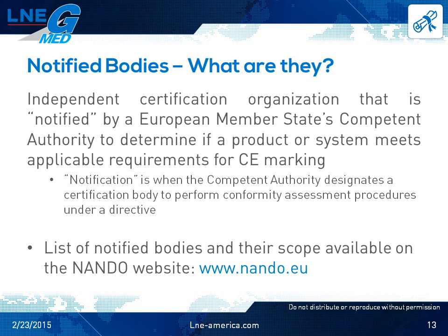So don't worry about accidentally contracting with a notified body that only handles, say, construction products to perform conformity assessments for your medical device. To see a list of all the notified bodies and the scope of their notification, you can check out the NANDO website at the address that you see. You'll be able to search both by body as well as by directive to check out which notified bodies are notified to which directives.